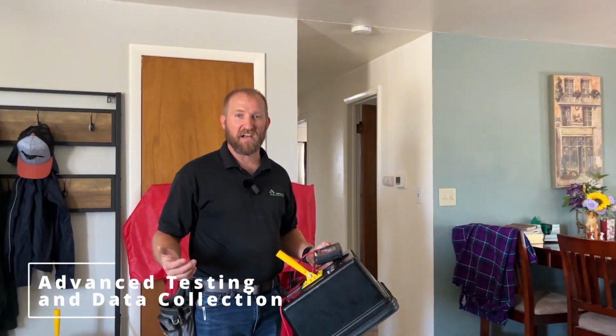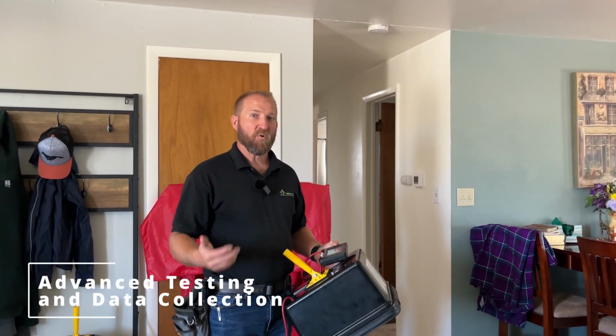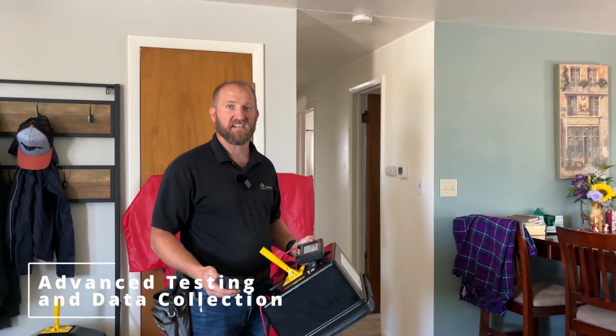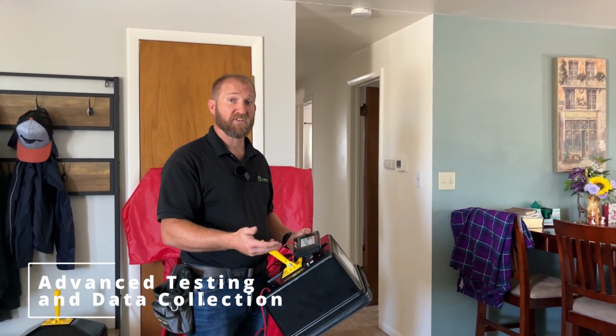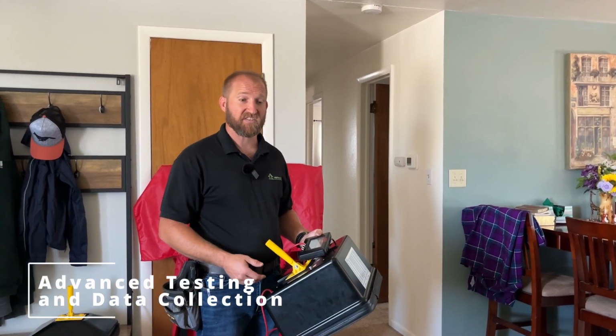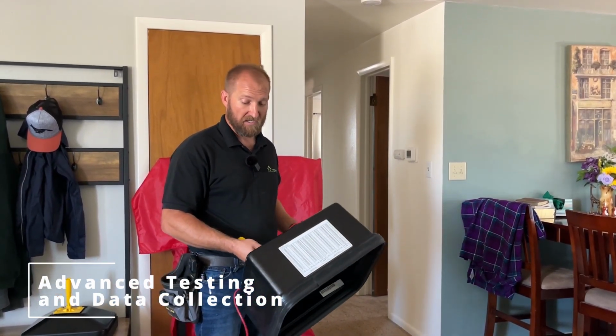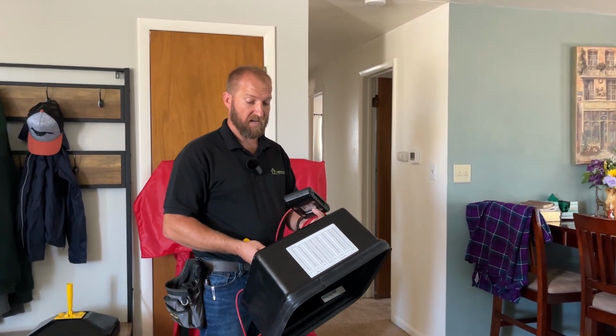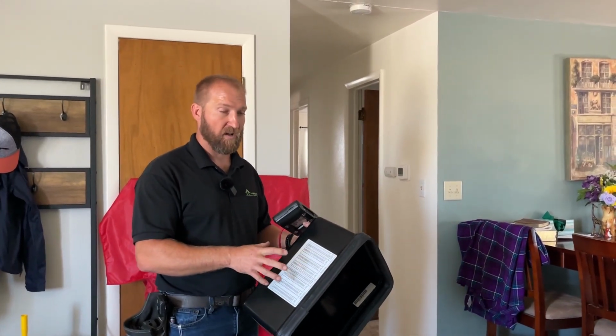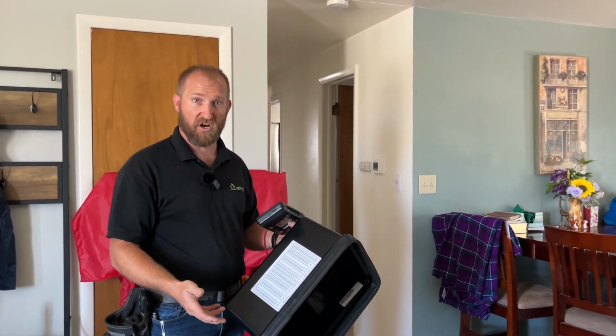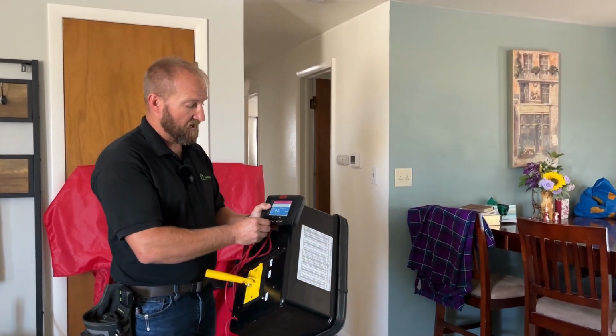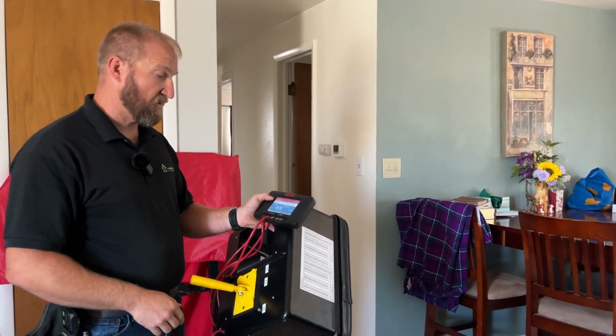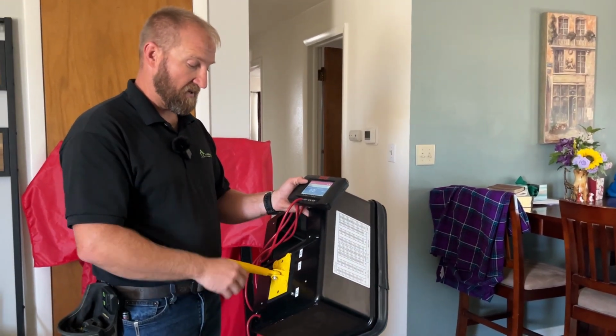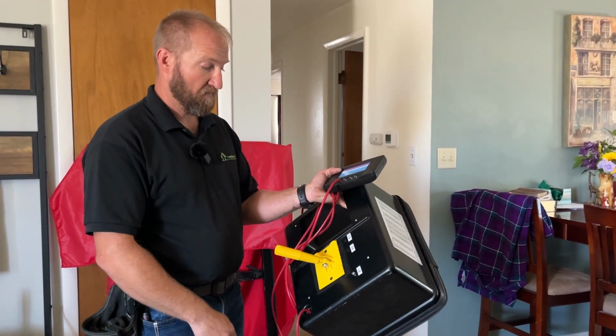All right, now that we've gotten the blower door out of the way, one of the other advanced tests that we can do either on a range hood or on the bath fans is utilizing our flow hood. Our flow hood is going to tell us how well a fan is exhausting. So we're going to set that up on the input tab on your manometer and hook it up to your flow hood.